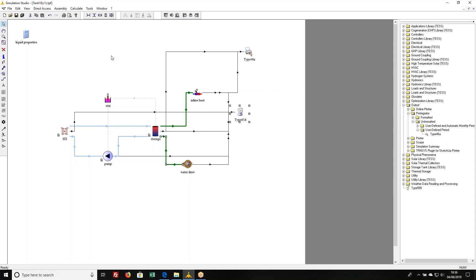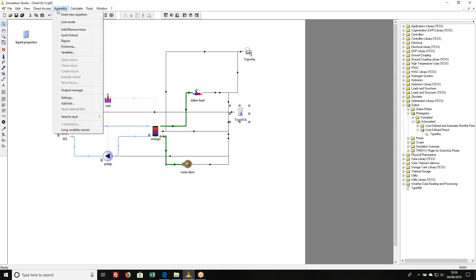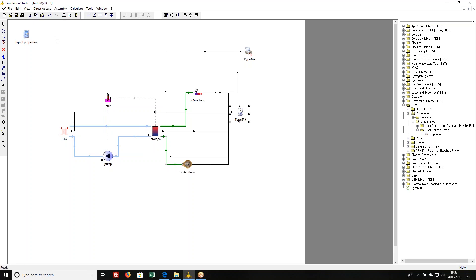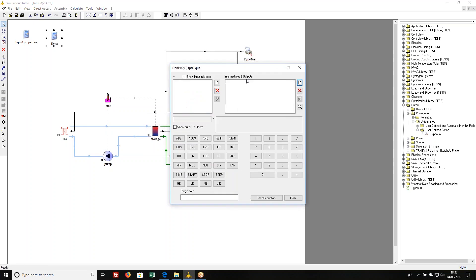And then I'll make a calculation of what nplots is. Now, it turns out that nplots is a built-in variable in TRNSYS 17, or in TRNSYS 18 rather. It's not in TRNSYS 17. If you're in TRNSYS 17 and you want to make it, it's essentially nplots is equal to two built-in variables, stop minus start, the quantity divided by, and then however many hours you want, 168. Or if you want daily plots, you can make, excuse me, not 124, but 24.